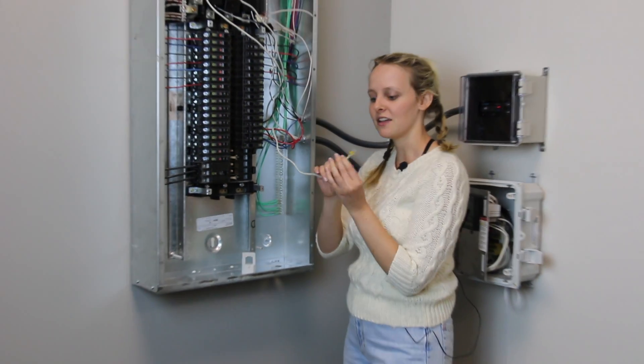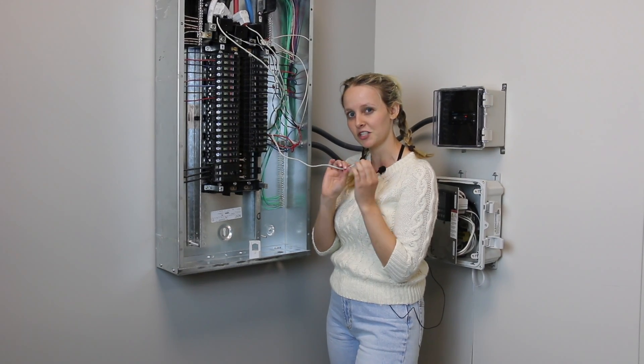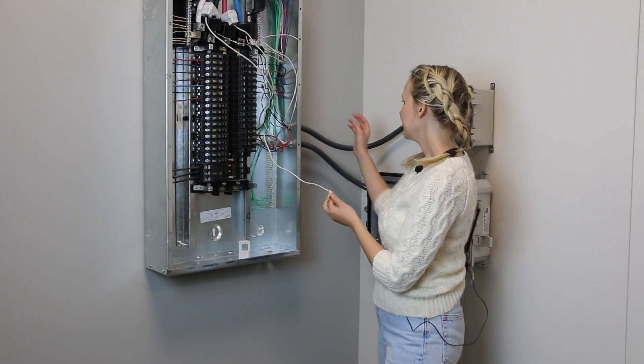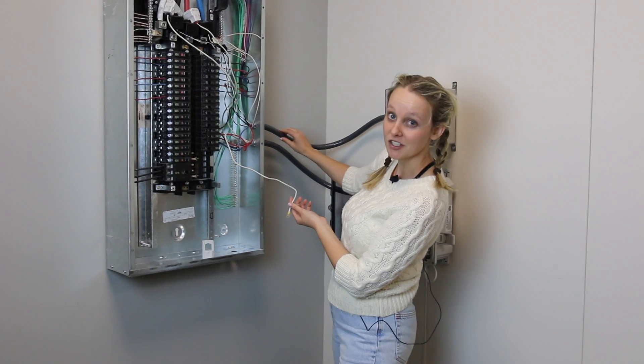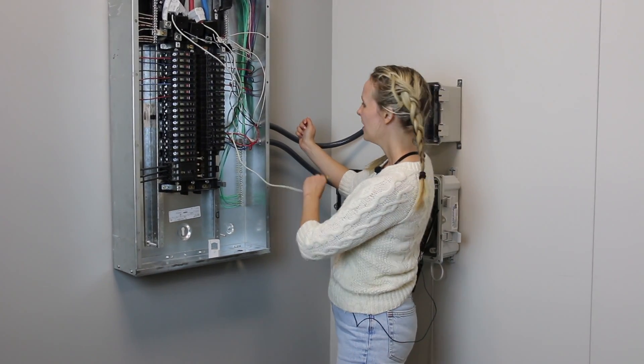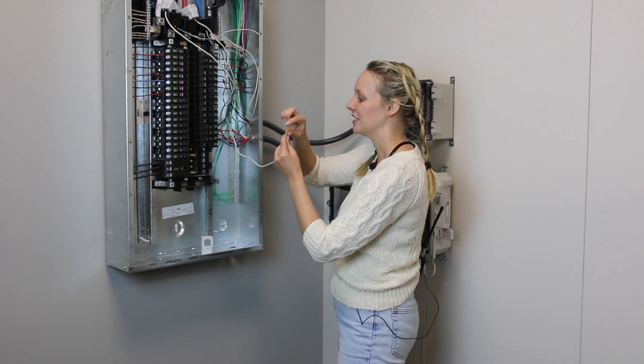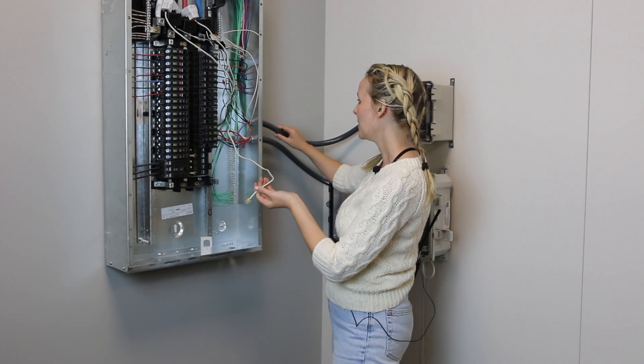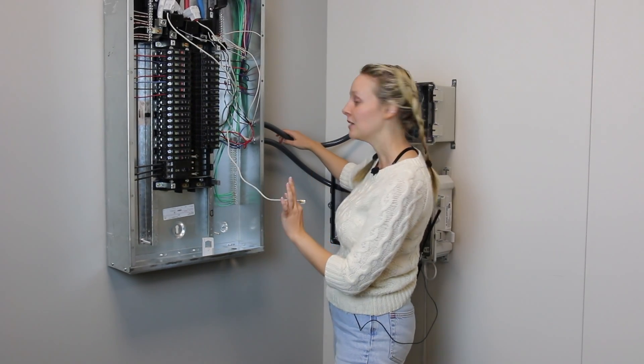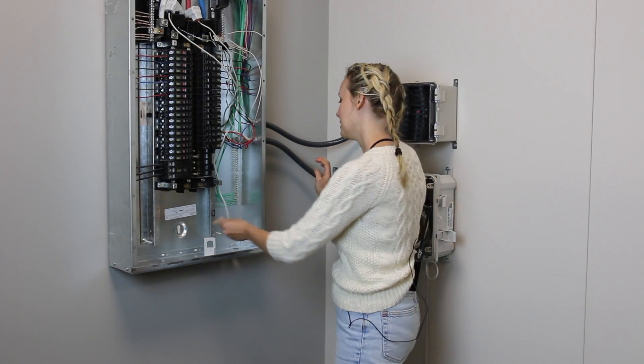One thing to note though is the RJ12 cable is a little more bulky than the traditional wires. We used half an inch conduit and what we found is it was kind of hard to thread all our wires through. We had to get three of these RJ12 cables through and especially the ends it was hard to get them. So I would recommend three-fourths an inch or above for the conduit you use when using these RJ12 cables.